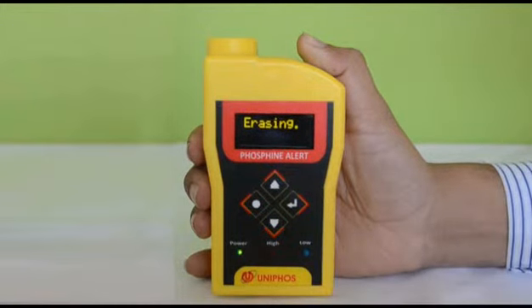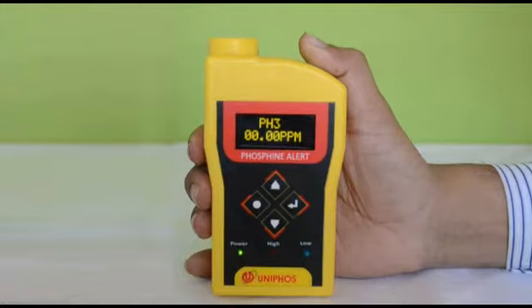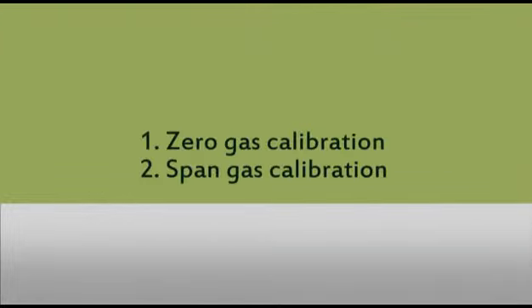Data can be erased by pressing the down key if necessary. Please note that this action will erase the data permanently. It is recommended to take backup of the data before erasing the data. Calibration mode. Calibration involves 2 steps: zero gas calibration and span gas calibration.